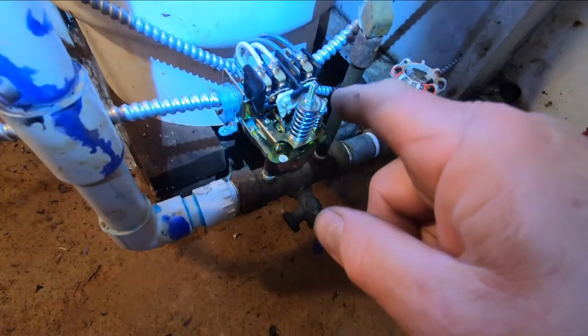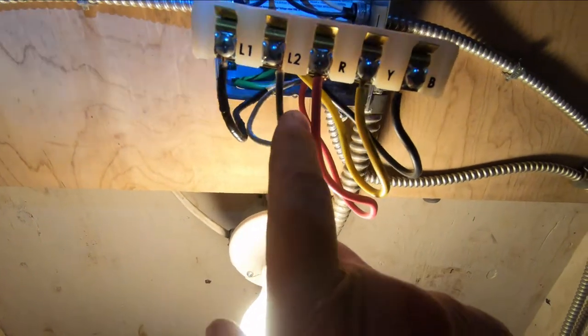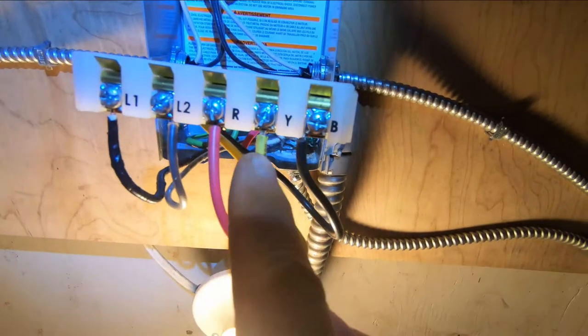When there's a demand created at the pressure switch, these contacts close, passing that current back up here to line one and line two in the control panel. Here's your leads from your pump - you have your three motor leads: red, yellow, and black.